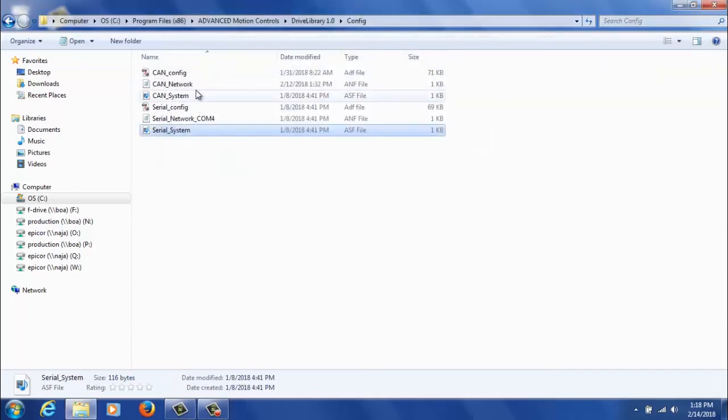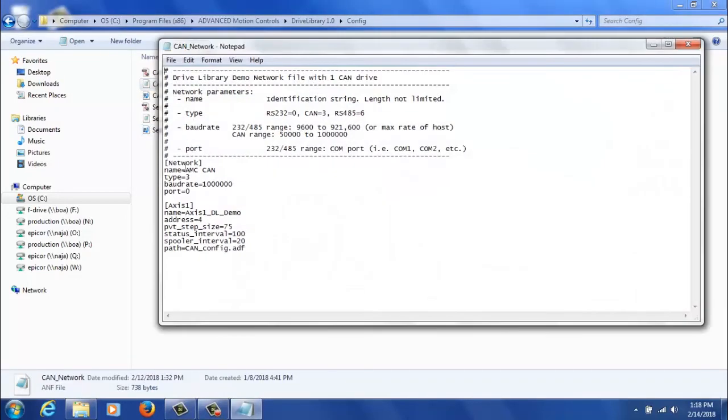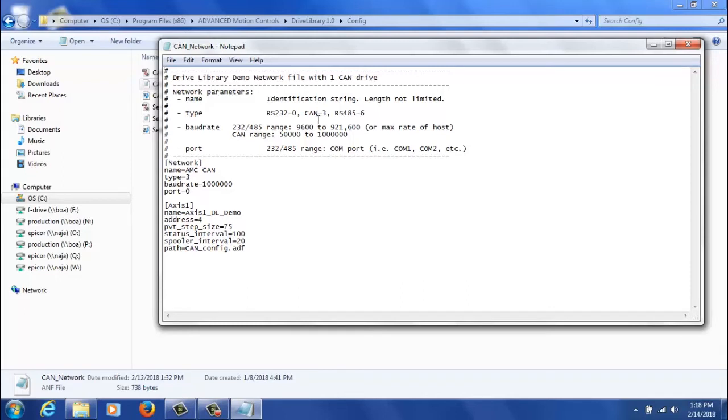On the CAN side, we'll go through a similar process, so we'll start with CAN network. And again, the first thing you'll edit is the network parameters. You'll give it possibly a unique name. The type will be 3 corresponding to CAN. And the baud rate will be whatever baud rate you set on the drive. And finally, the port will be the port that you find in Device Manager for your CAN drive.